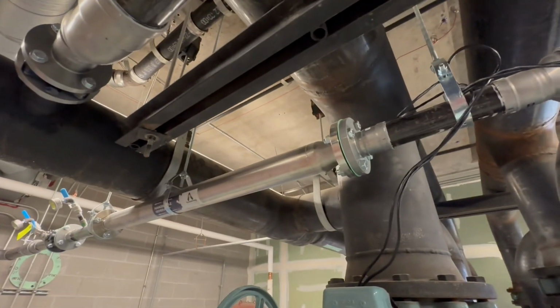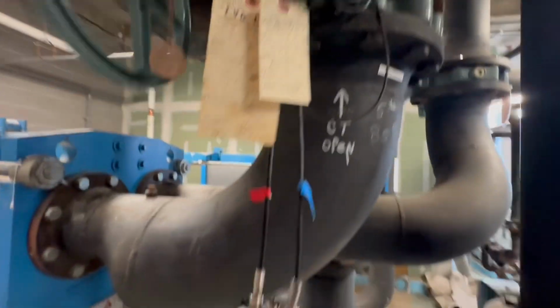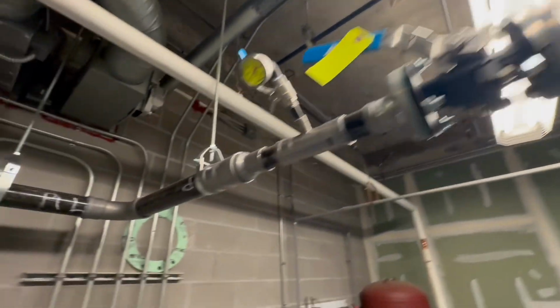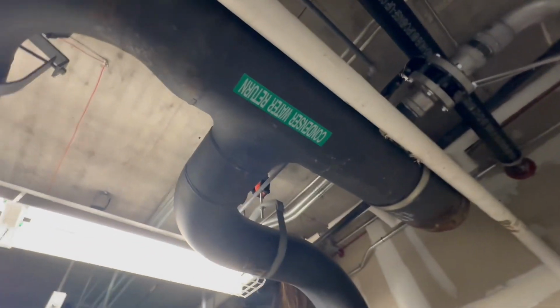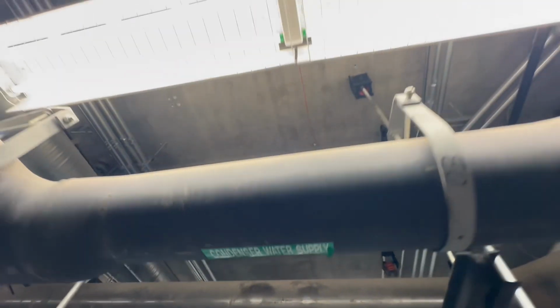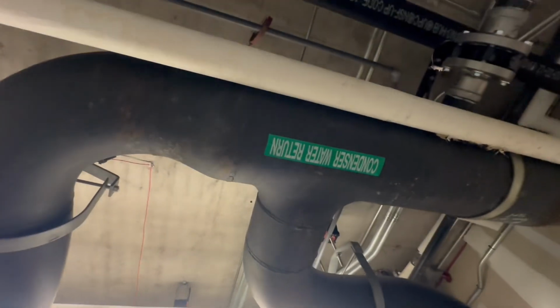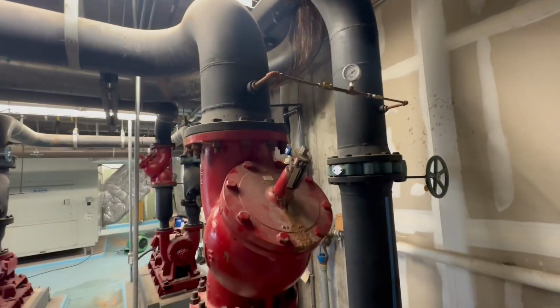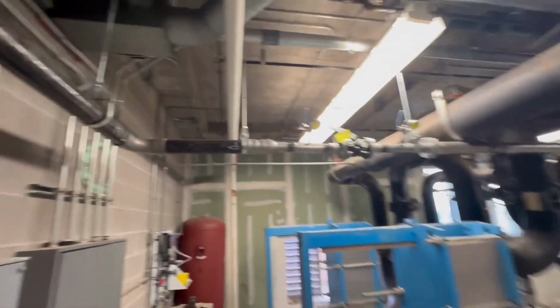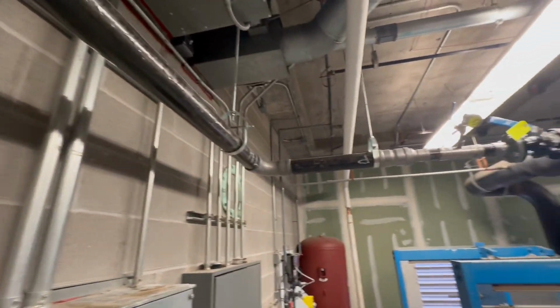Again, we have a 2-inch nanobubble generator currently running at 87 gallons per minute. That runs through a balancing valve around here. Then we go right back into the suction header. So this is the condenser water suction header. So remember, we're pulling off of the condenser water supply header, and we're returning right back into the condenser water return header using the differential pressure that's generated from the condenser water pumps to create flow. So we have no additional pump required for this system.